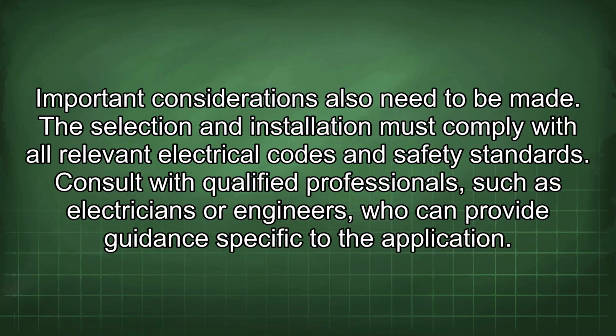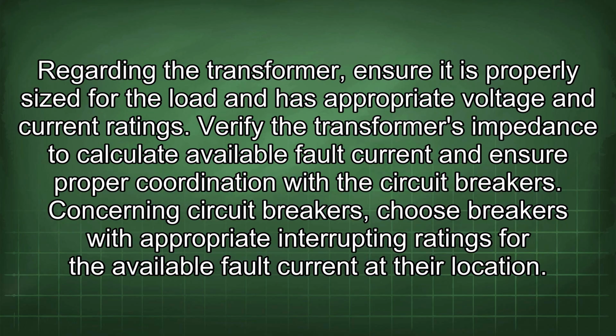Important considerations also need to be made. The selection and installation must comply with all relevant electrical codes and safety standards. Consult with qualified professionals such as electricians or engineers who can provide guidance specific to the application. Regarding the transformer, ensure it is properly sized for the load and has appropriate voltage and current ratings. Verify the transformer's impedance to calculate available fault current and ensure proper coordination with the circuit breakers.